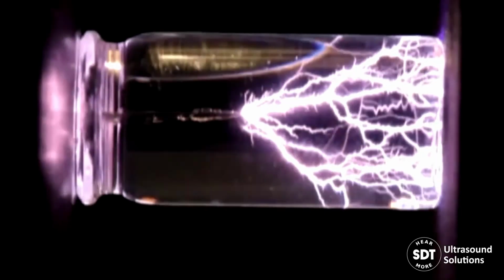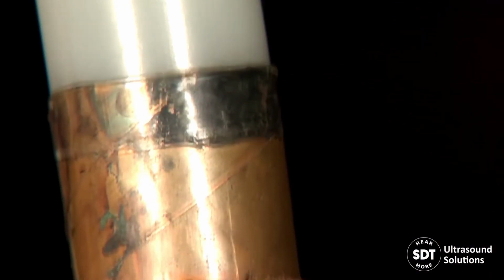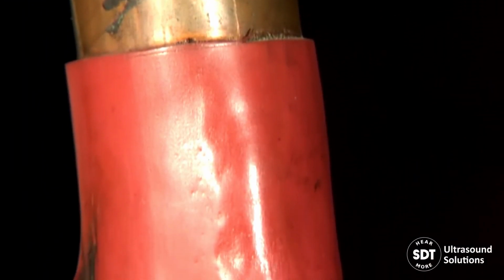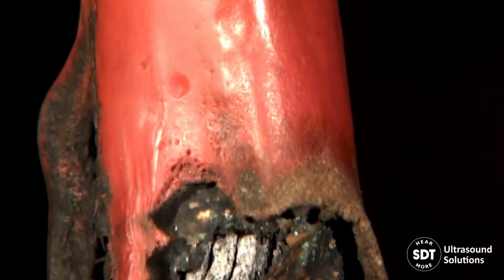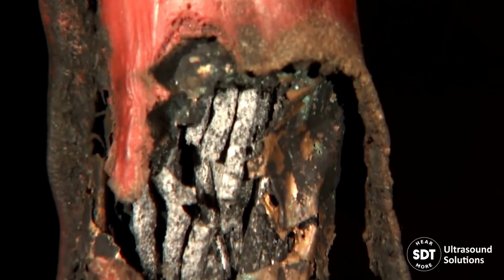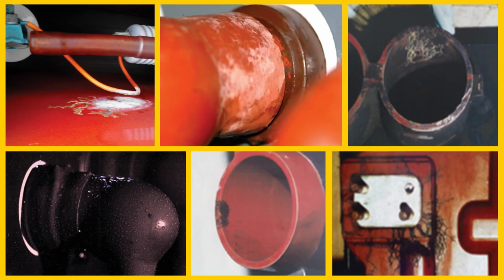Partial discharge emits energy in several ways, producing electromagnetic emission in the form of radio waves, light and heat, acoustic emission in the audible and ultrasonic ranges, and ozone and nitrous oxide gases. These emissions enable us to detect, locate, measure, and analyze partial discharge activity so we can identify faults before they develop into failures. Partial discharge activity may be intermittent, or it may vary in intensity over time, but once it starts, one thing's for sure. The damage is always going to increase. It's not going to get better.